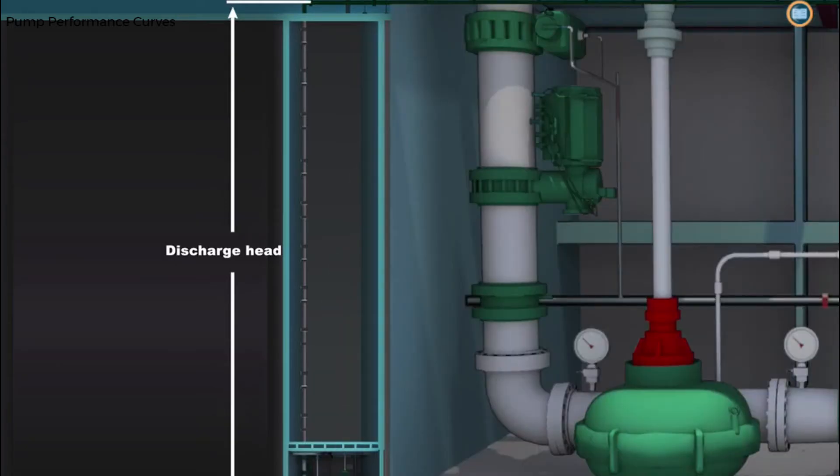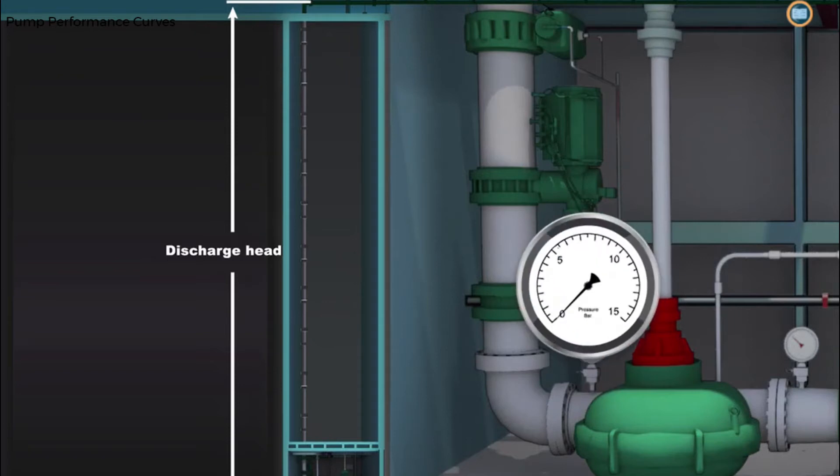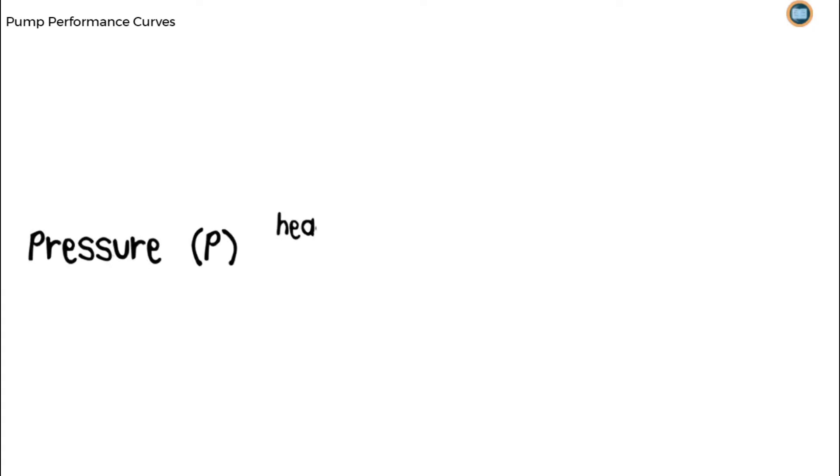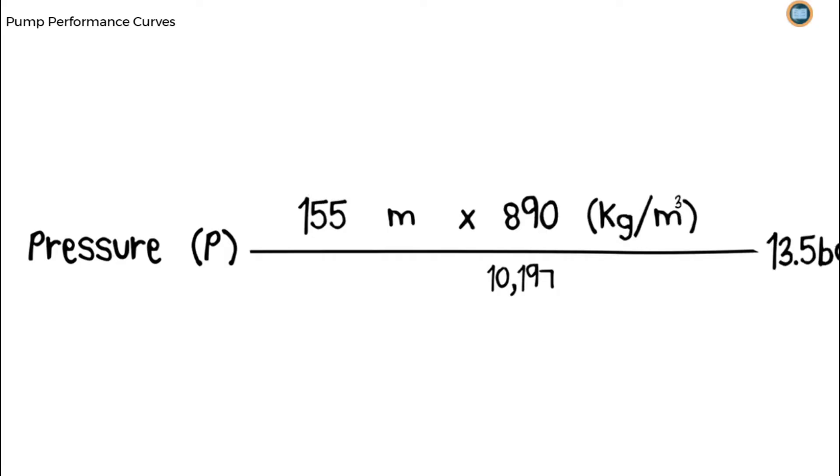This is usually measured in meters, but can be converted to the more familiar units of pressure known as bar. We do this by multiplying the head by the density of the liquid being pumped and dividing it by 10,197. For example, a head of 155 meters and a density of 890 kilograms per meter cubed would be equivalent to a pressure of 13.5 bars.